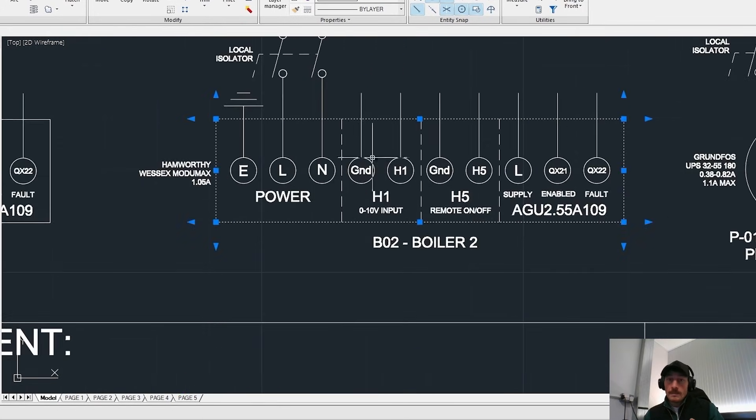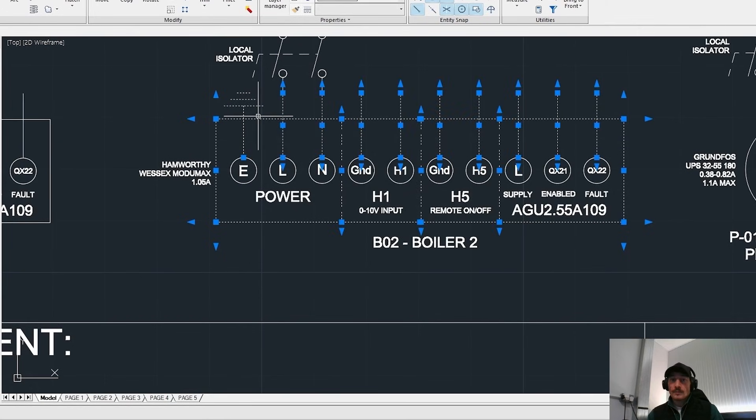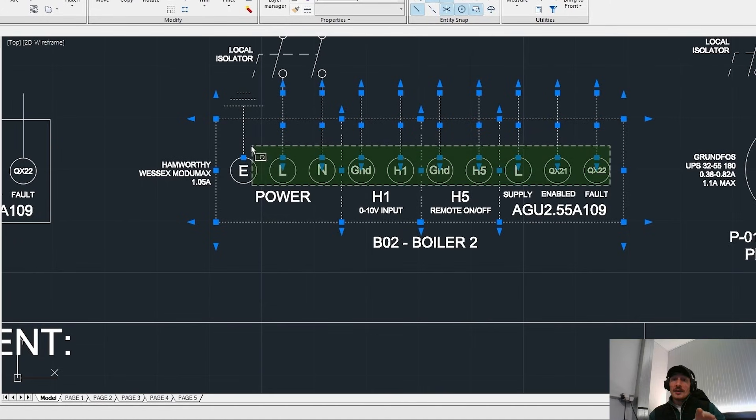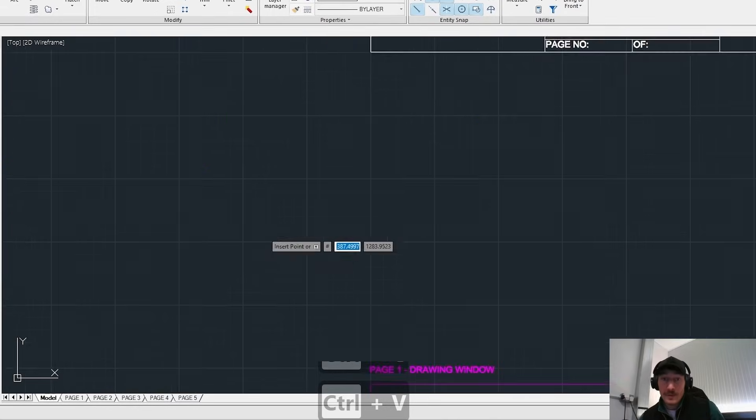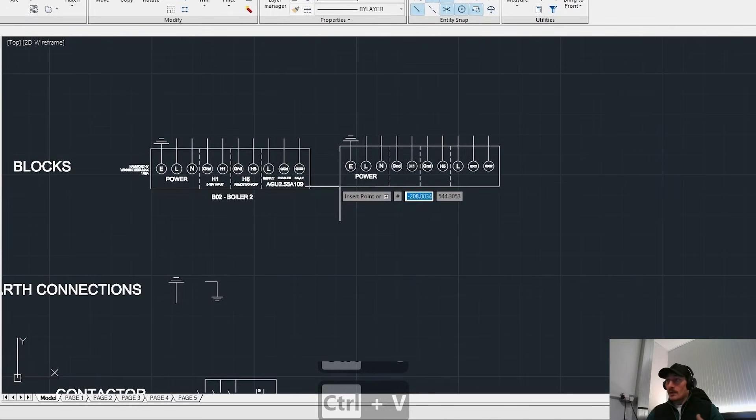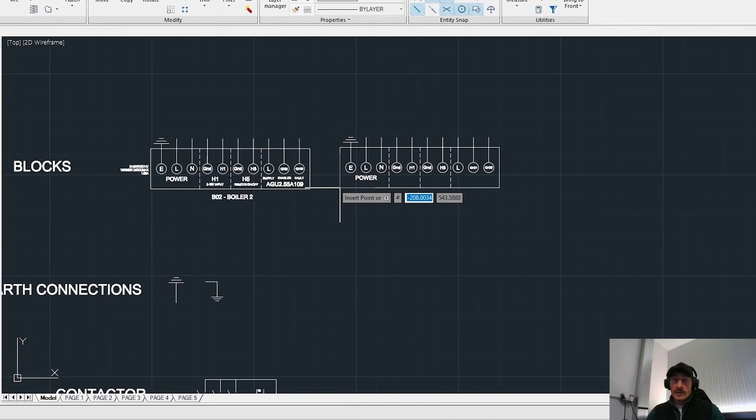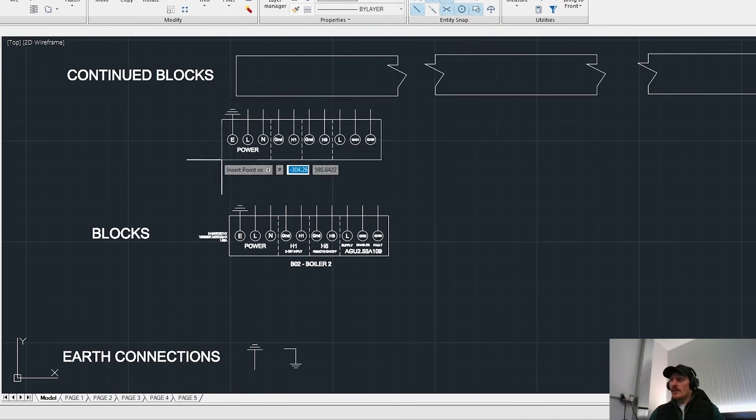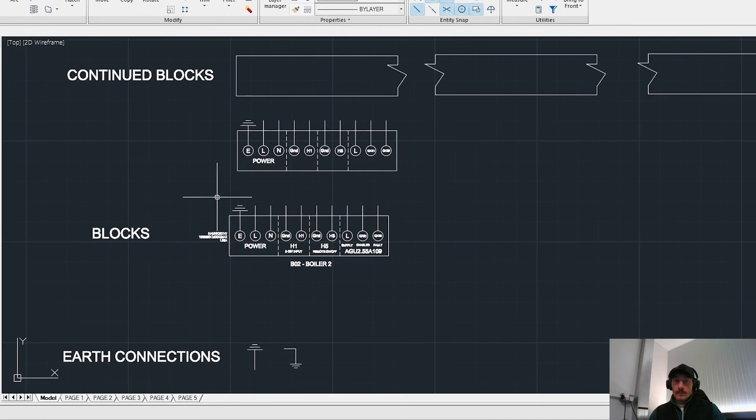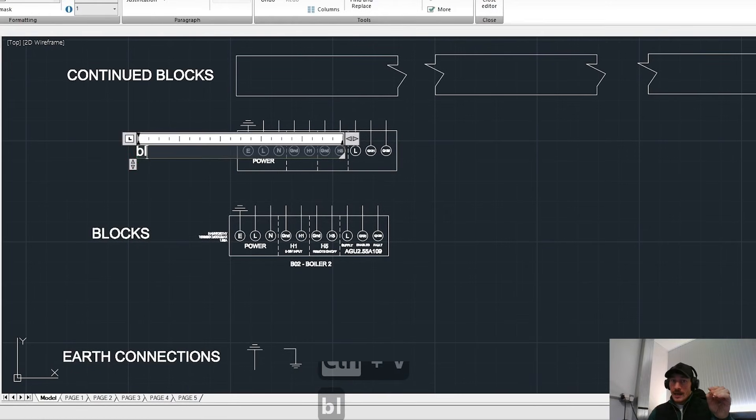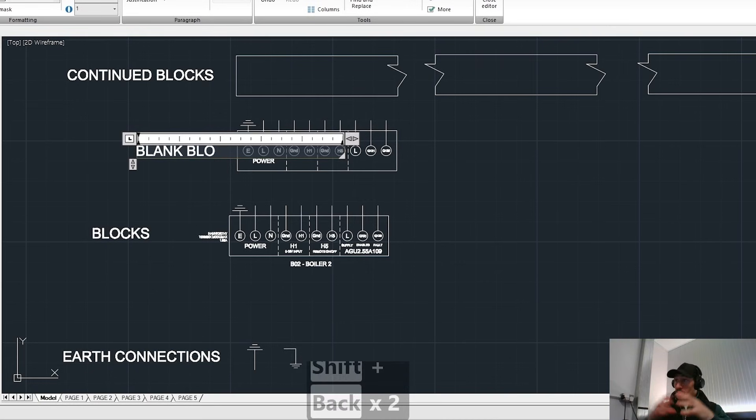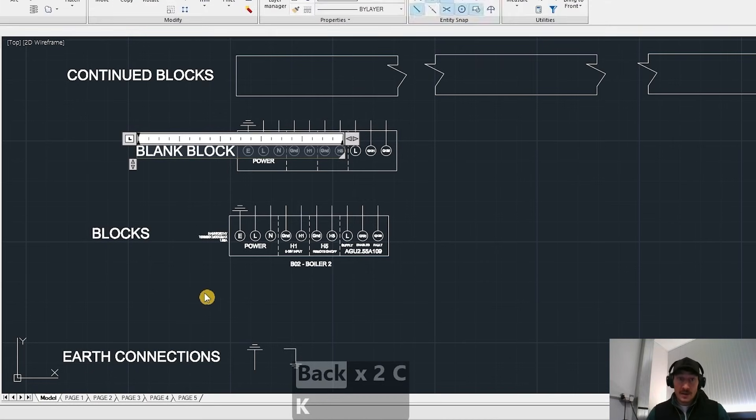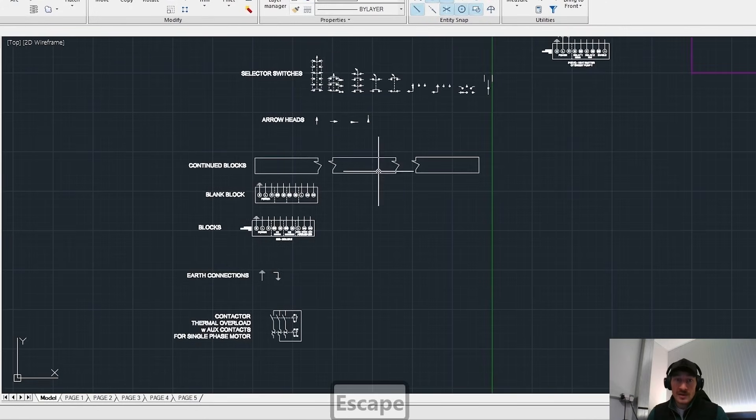Now what we're doing is we're going to be designing a smart pump. And the way that I designed these smart pumps, they're not like a standard circular motor symbol because there's various inputs and outputs for these smart pumps, where you have like running outputs, you have fault outputs. You might have a constant power connection and then you have a run enable on and off. So for that I just create like a block like you're seeing here and then detail all the connections.